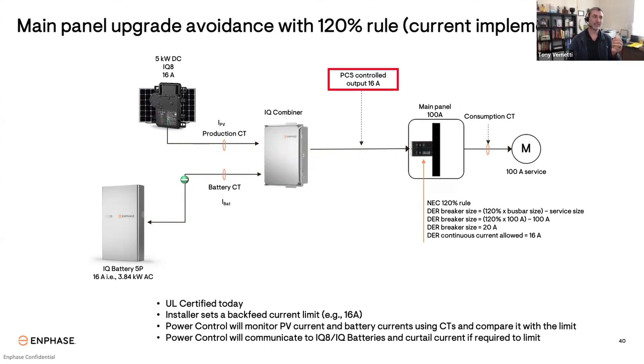This feature can be applied to a solar-only system or a solar system with batteries. This works pretty well for systems that have batteries and solar, because the batteries and solar are rarely actually backfeeding the main panel simultaneously. During times of high solar production, the battery is normally being charged by solar. So the electrical current from solar isn't backfeeding to the main panel. It's going through the combiner into the battery. Now that brings me to the downside, or the Achilles heel of this current implementation, is that during times of high solar power output, such as midday in the summer, the power output might be curtailed, and the system would produce less energy than it potentially could. This effect is a lot more pronounced with solar-only systems, since solar is backfeeding the main panel at all times.